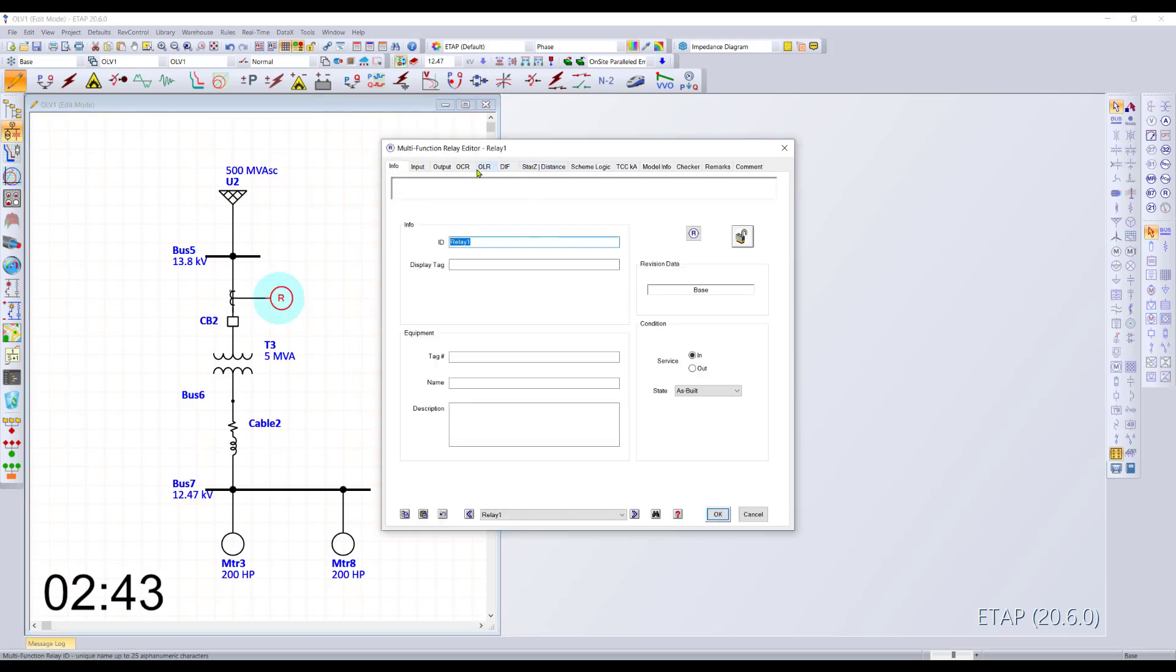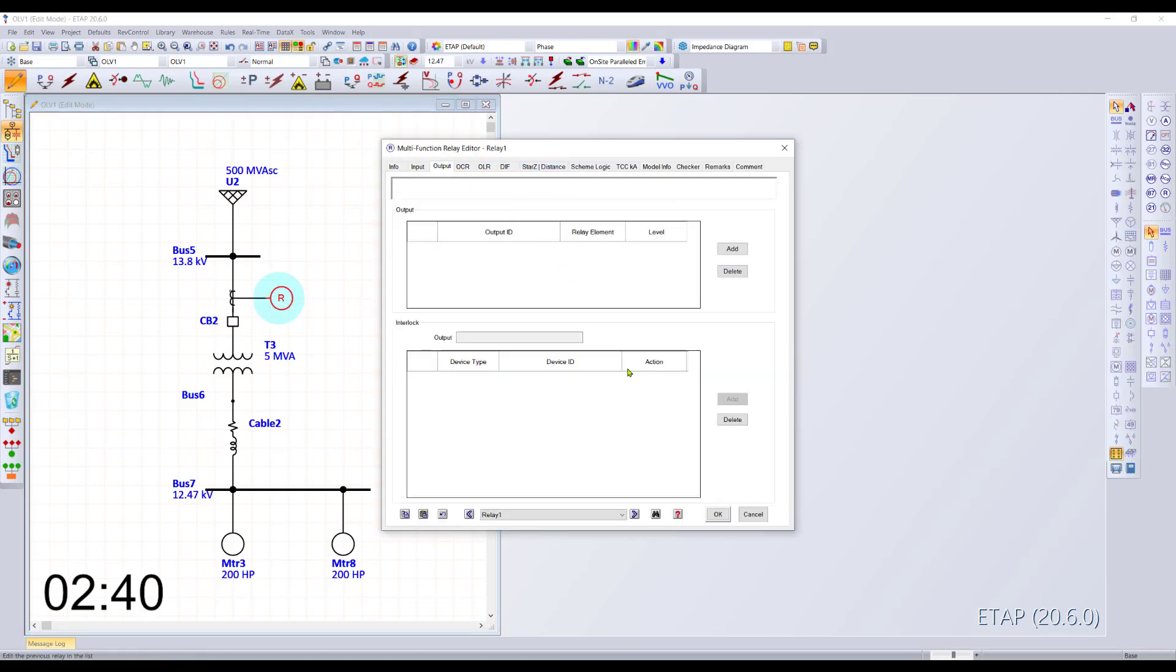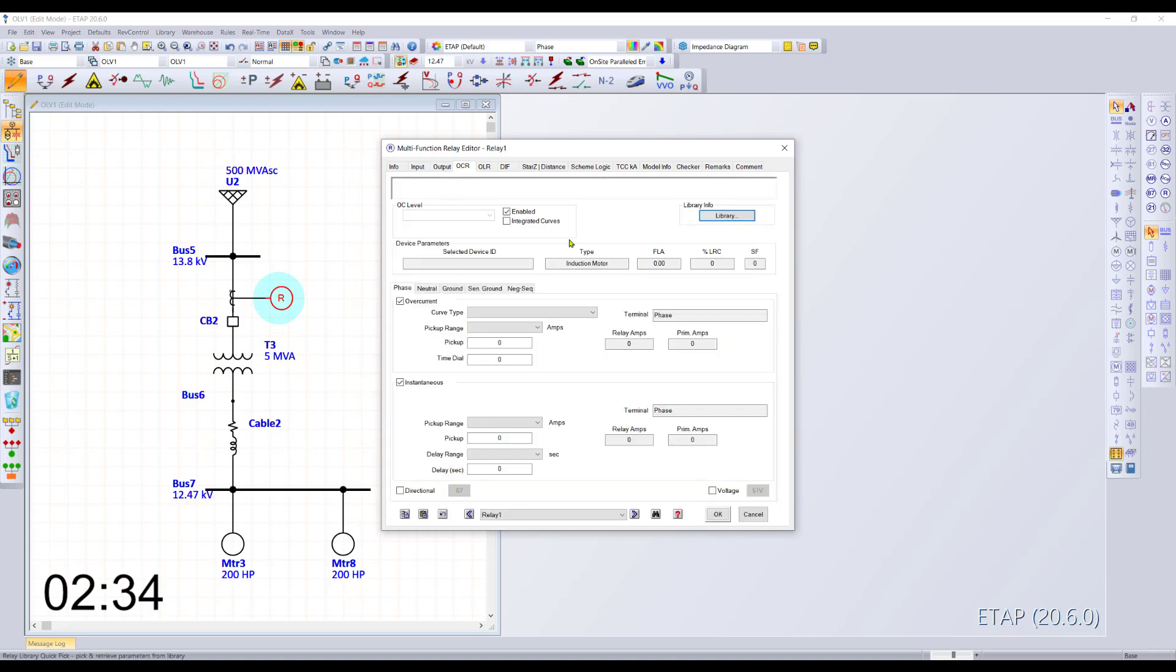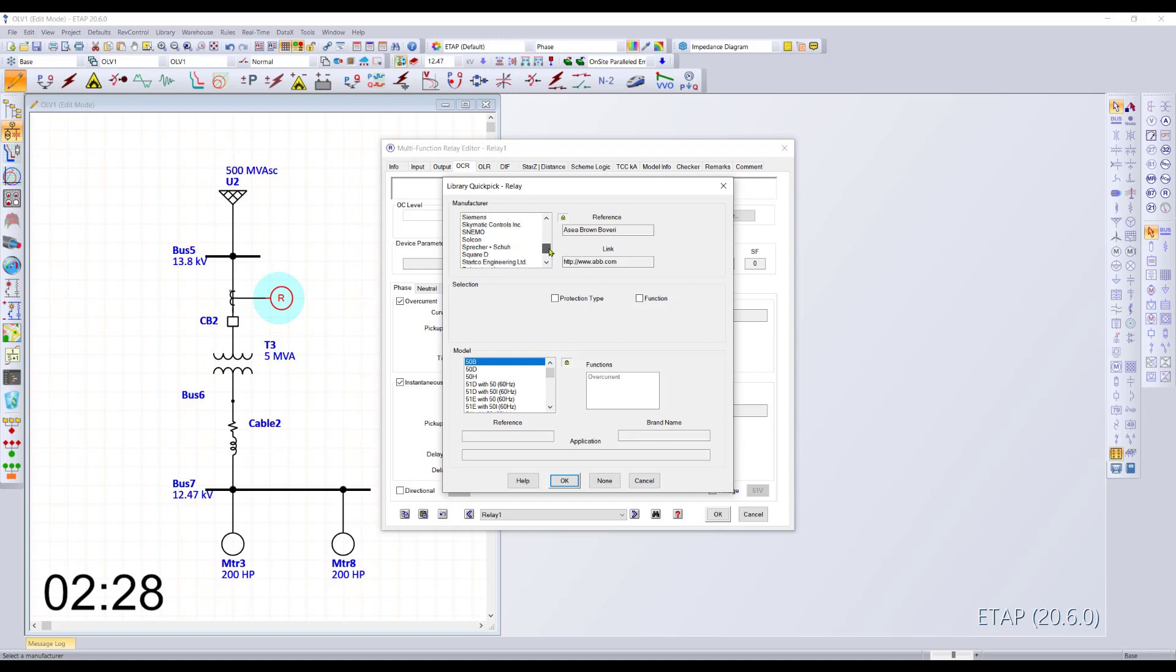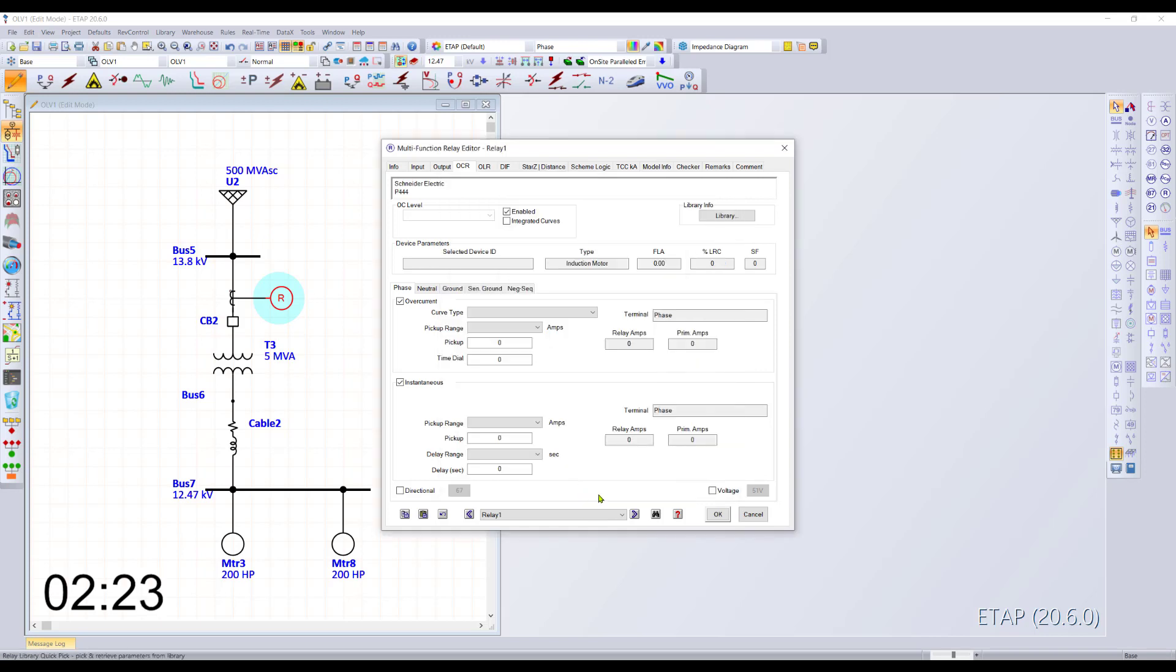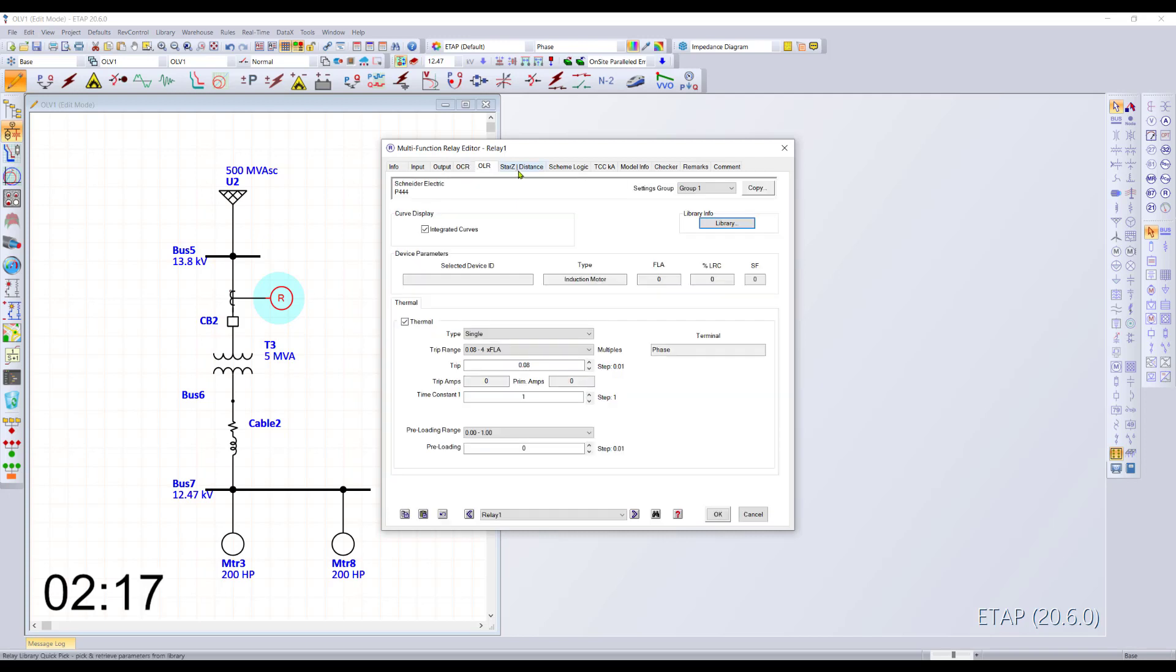Now we can go back to defining the output for this relay, which needs a digital output. It's going to be circuit breaker number two, so that's automatically interlocked for me. From the library, which is verified and validated, you can pick from all of these different vendors and pick your favorite vendor. We'll pick a Schneider relay, which is a Micom. It sets up the relay based on its functions - OCR, OLR, as well as distance functions.